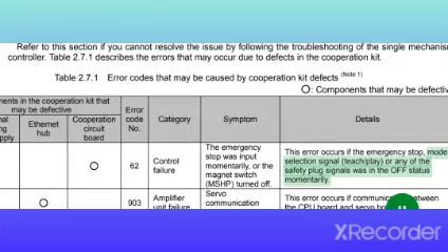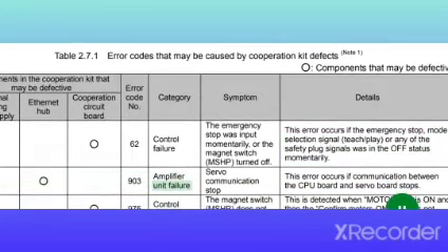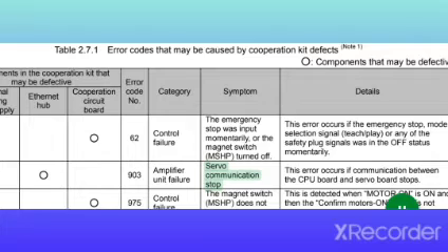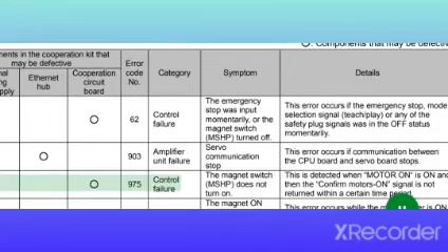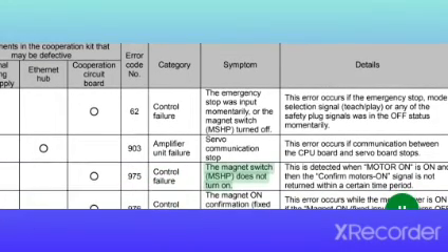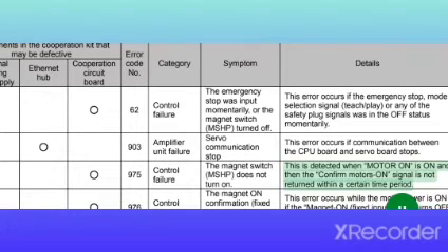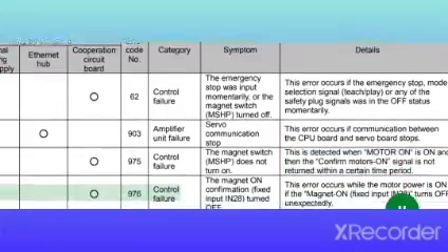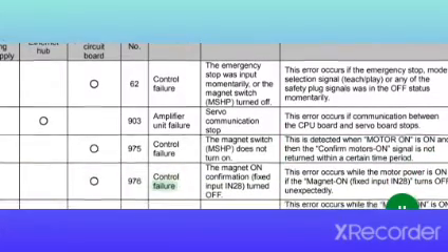the off status momentarily. 903 amplifier, unit failure, servo communication stop. This error occurs if communication between the CPU board and servo board stops. 975 control, failure. The magnet switch MSHP does not turn on. This is detected when motor on is on and then the confirm motor's on signal is not returned within a certain time period. 976 control, failure.